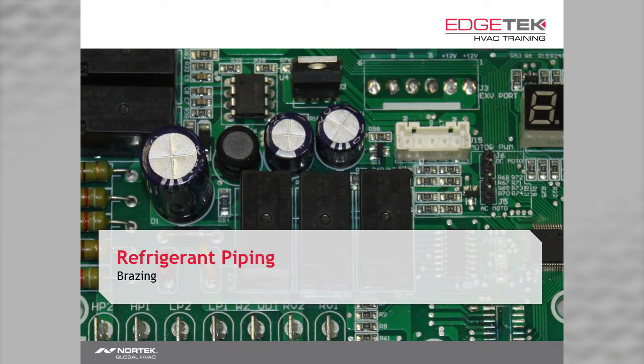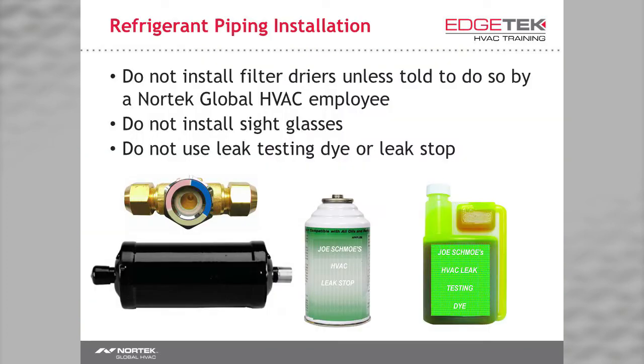That's a fact, obviously. But even brazing experts like us need to brush up a bit. First off, do not install sight glasses. They'll show you absolutely nothing useful. Take your youngest tech, right? Send him out on a unit with a sight glass. If he sees bubbles in the sight glass, what will he do? That's right, he'll add refrigerant. Don't add one, and he won't just automatically add refrigerant.